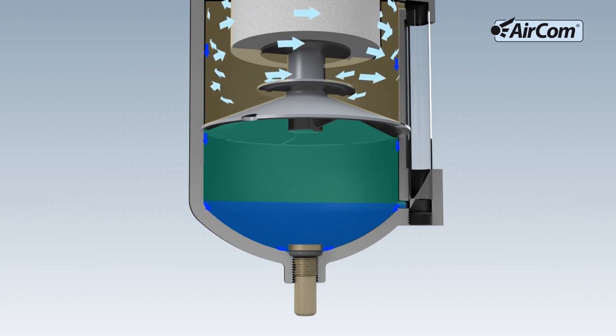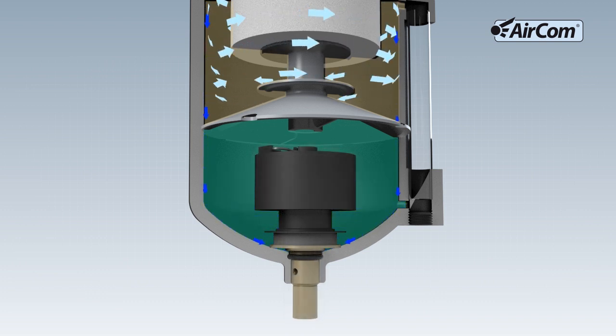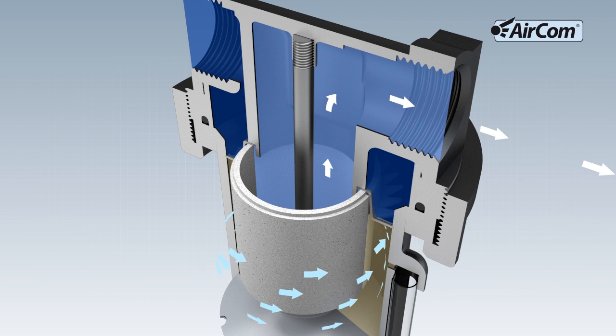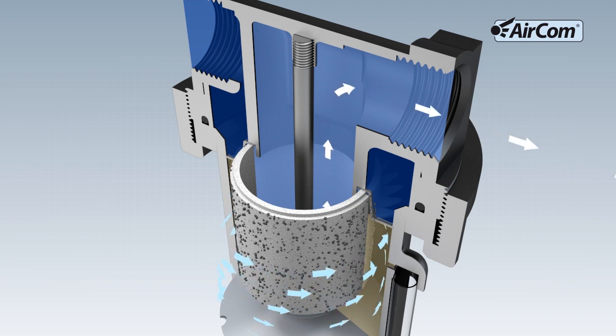The condensate collects in the slowdown zone and can be removed from the filter using a manual drain or an automatic drain. The air from which the condensate has been removed now flows through the filter element to remove the remaining dirt particles.